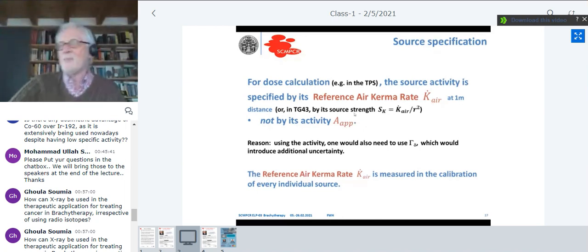The reason for that is that if we used the activity, we would always also have to multiply by an air kerma rate, and with an air kerma rate constant we would always introduce additional uncertainty, because there is uncertainty in all of the steps to determine gamma, this number gamma. So we don't use the activity.